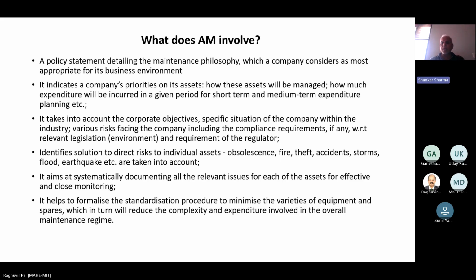Now, we can apply this asset management philosophy to each major equipment. What I used to do at the Karnataka Electricity Board back in India was maintain a transformer register - for all transformers under my administrative control, we kept a register with manufacturing and technical information about each transformer on its own page. Additional pages recorded major parameters over time, such as whether it tripped on its own, whether it failed, or was repaired. Yearly, I would do online or offline condition monitoring of the transformer without taking it out of its place.